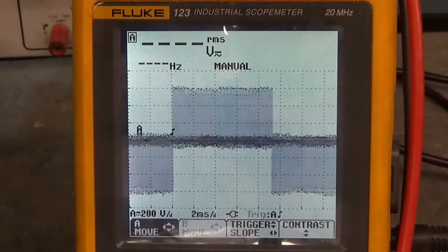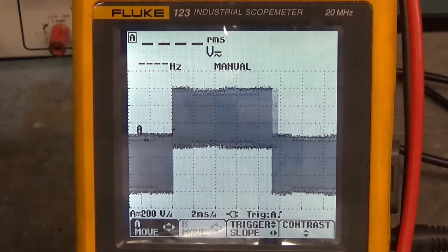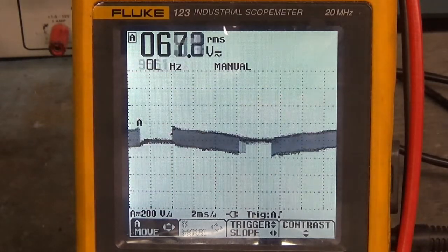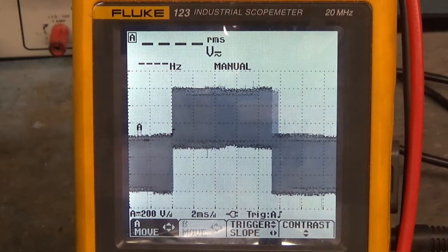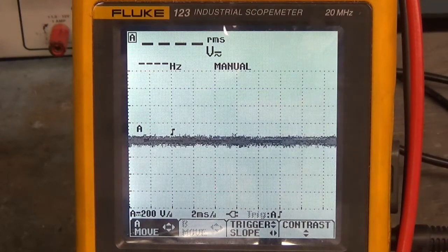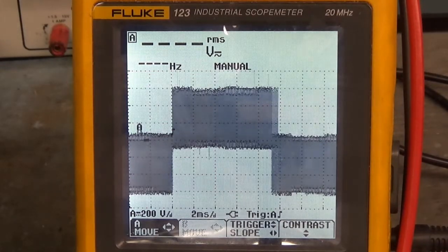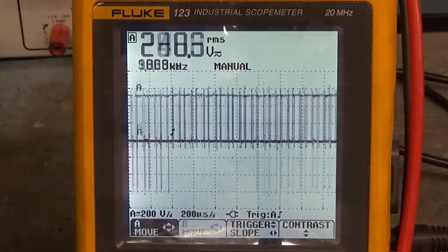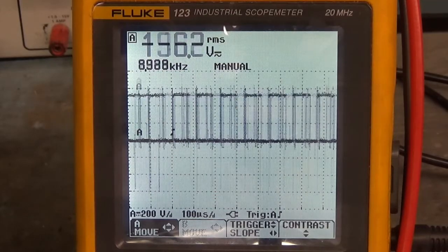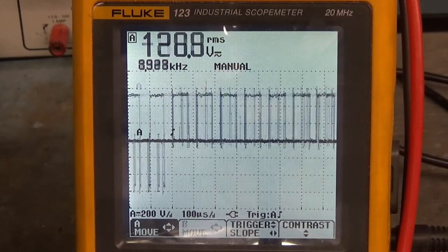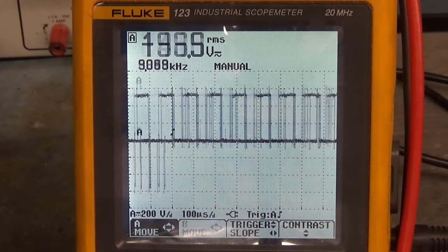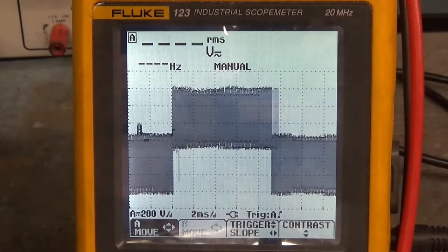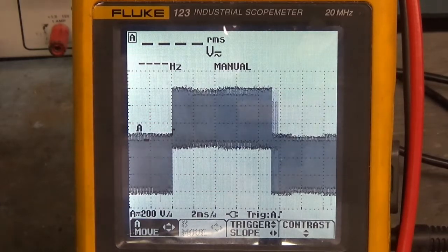We need to move the camera so you can get a close up of those waveforms. All right, here's U to V. This is U to W. And here is V to W. I'll spread that waveform out. We'll look at the pulse width modulation. Look at that, ain't that pretty. Those are the waveforms that run that motor. Let's pull it back in.